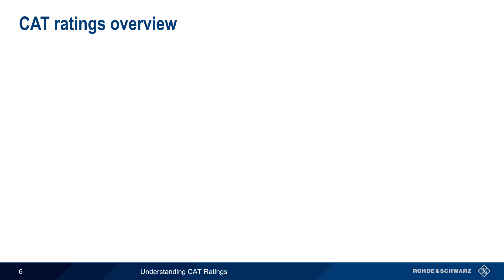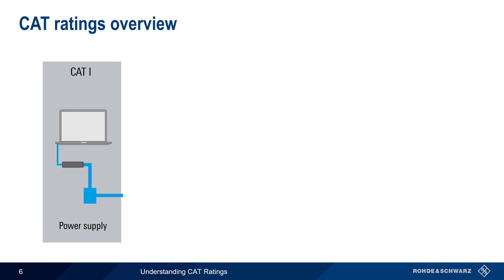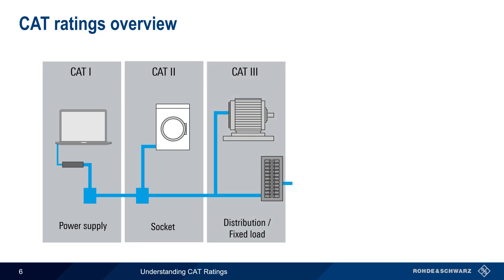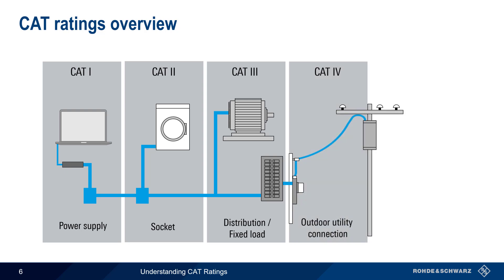There are four CAT ratings. CAT 1 applies to measurements of devices that are not directly connected to mains power. CAT 2 is needed when measuring devices that are plugged into standard sockets or receptacles. CAT 3 applies to both fixed loads that are directly wired into mains, as well as to power distribution elements such as breaker panels. And CAT 4 applies primarily to the outdoor utility connection. Note that the higher category numbers indicate closer proximity to the voltage source. In the next portion of this presentation, we will go through each of these categories in more detail.